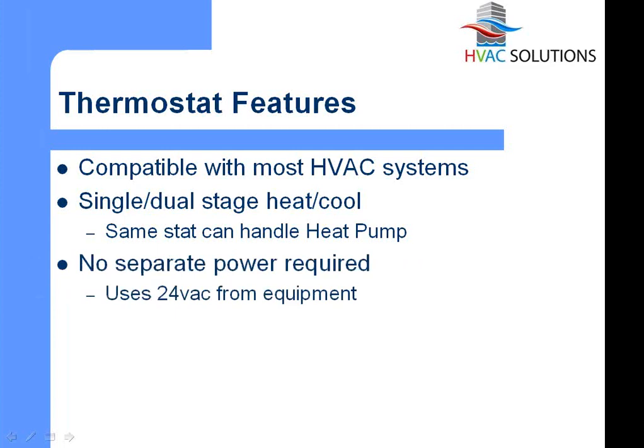These stats are sold in 2 different ways. They are sold with Ethernet powered thermostats, where power actually comes over the Ethernet wiring to the stat, and they are sold as HVAC powered stats, which is where we power the thermostat with 24 volts from the furnace or from the rooftop. The ones that we stock and use here at HVAC Solutions and TEC are all the 24 volt versions. We can get you the Ethernet powered if you want it for some reason, but 24 volts is probably the way to go. Power it off the furnace. You don't want the power of the thermostat to be related to what's going on the Ethernet connection. If you lose the Ethernet connection, you don't want the thermostat to stop providing heating and cooling. So it's better to have the power on the HVAC side of the equation. Plus, then you don't need any additional special gear to power it. Just the thermostat wired to the furnace or the rooftop.